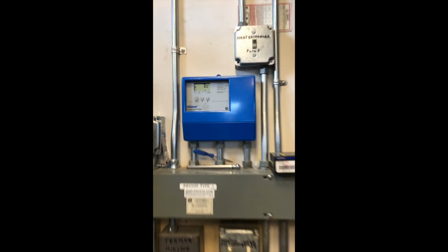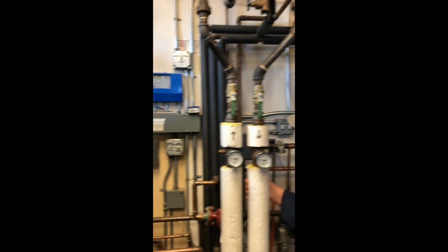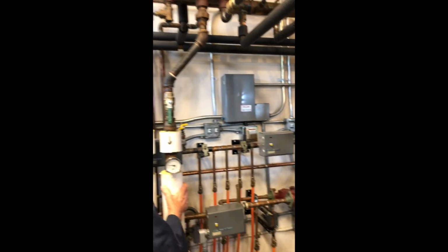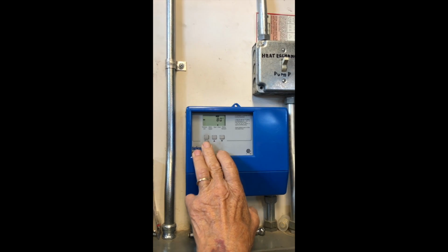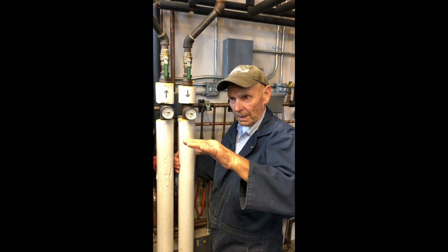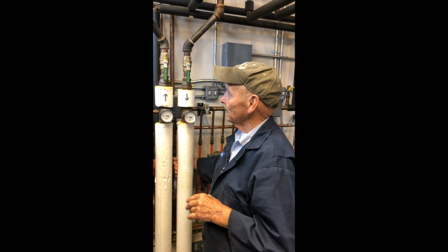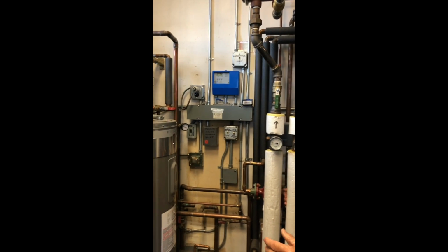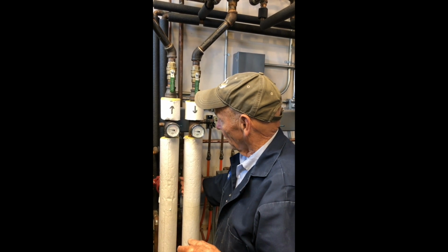Right now it says 80 on here. What does that mean? That means we're not calling for heat and the system is only 80? Yeah, it's not calling for heat. You can select the boiler temperature here by going to boiler or going to system. It does a really good job of handling the 120 degrees and modulating back and forth to give you that. It's been faultless ever since I've had it in, over 14 years or something like that.